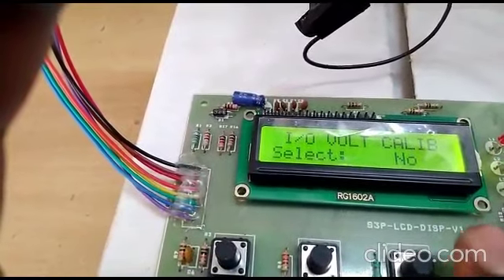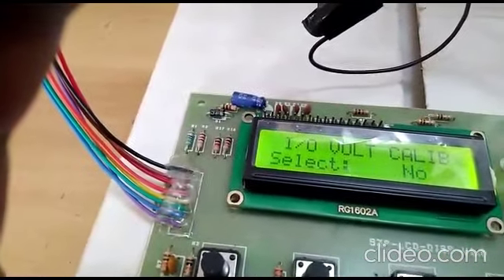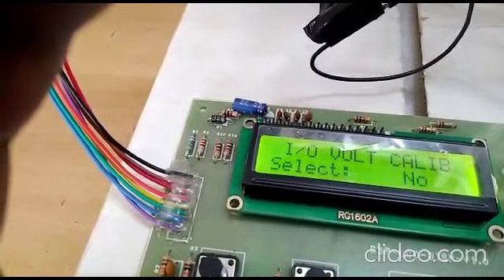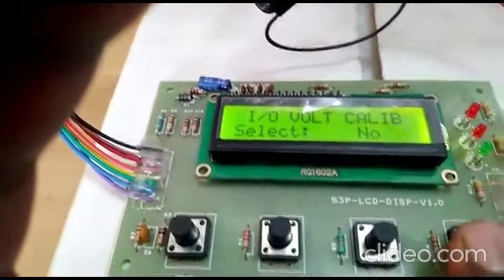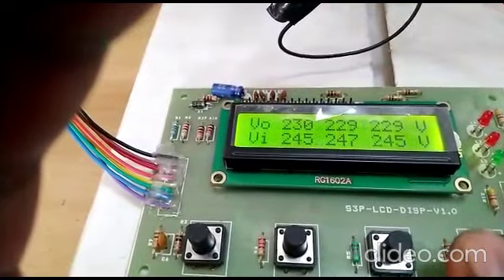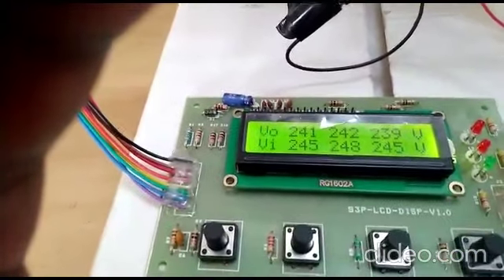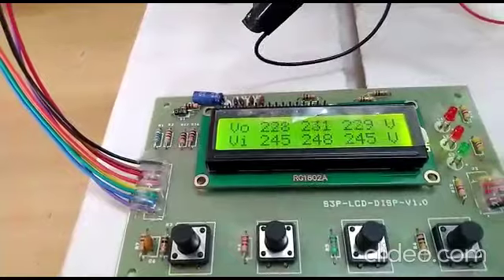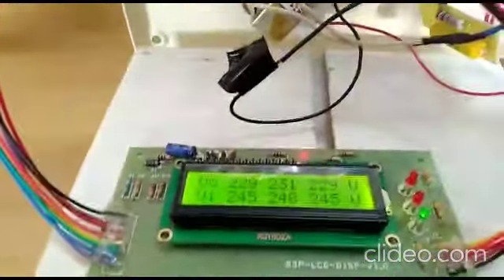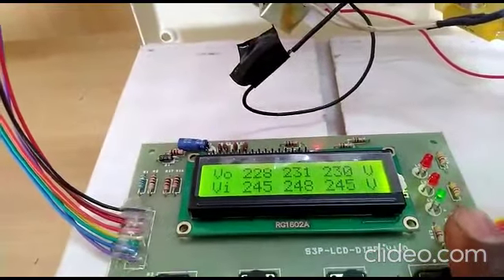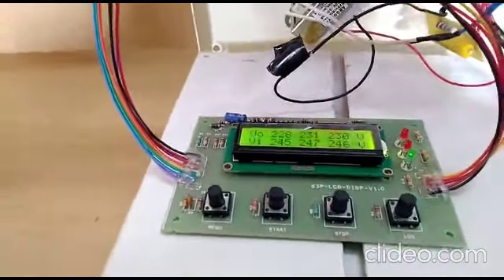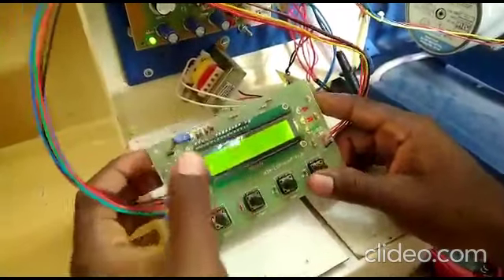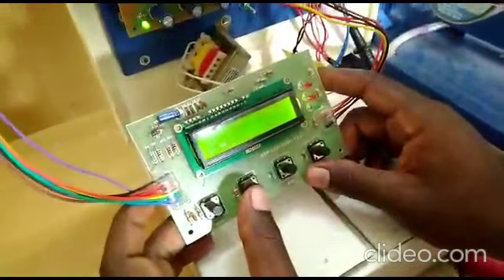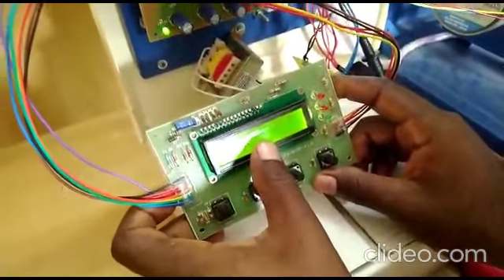The next is input output voltage calibration. If there is no need for input or output voltage calibration, just put no and press the next button, saving the parameters. It will automatically exit from the setting mode. The output LED is going to turn on. This output LED will also turn on. Okay, done.